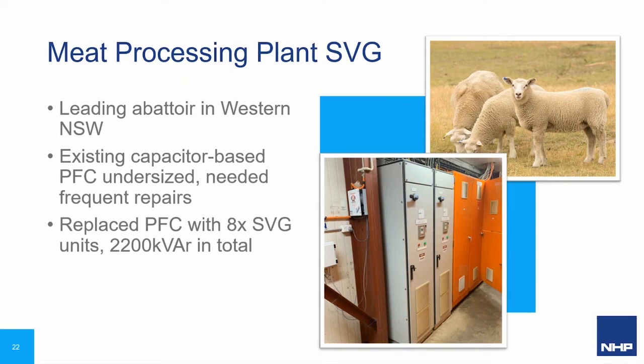So then we discussed the SVG technology, which plays exactly to address those problems they had experienced, with no mechanical moving components such as the contactors, and the lack of or non-existent capacitors in the SVG technology, so they've moved away from having that consumable issue and that big overhead cost. And then also with the dynamic response time with the SVG technology, the efficiency gains that they were able to get with that dynamic response time was an added benefit. Now, they were really welcoming to that technology.